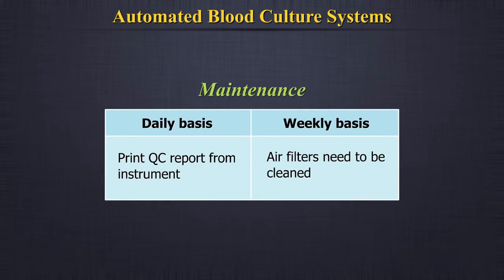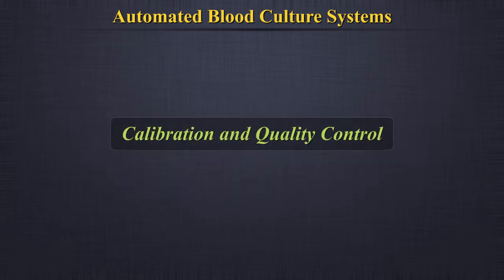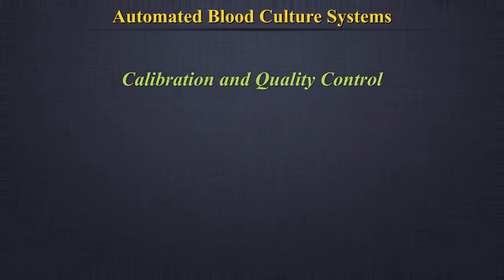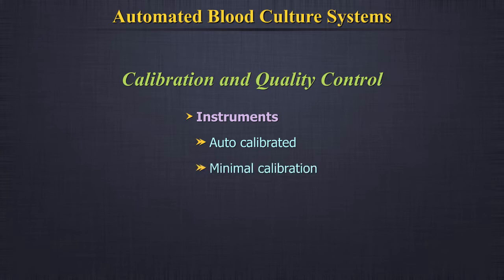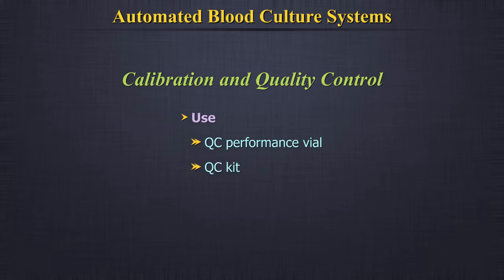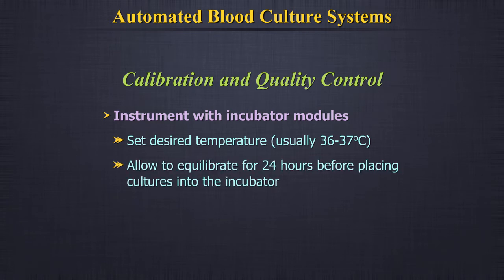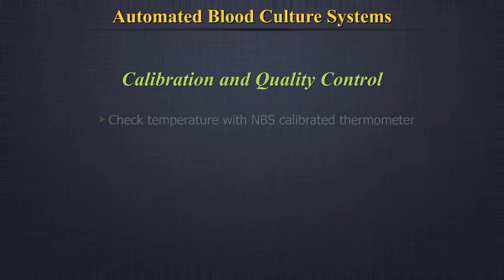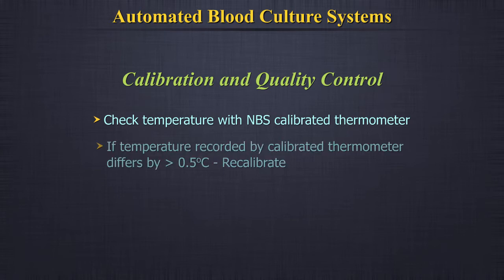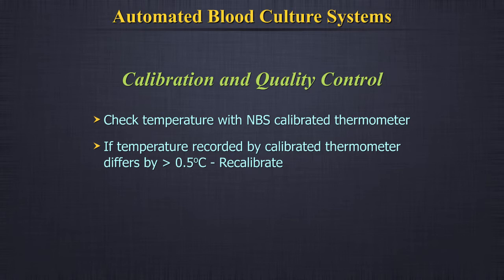Daily or weekly maintenance: on a daily basis, it is required to print the quality control report from the instrument, and on a weekly basis, air filters need to be cleaned. Calibration and quality control: the manufacturer will provide a service representative to perform initial installation and calibration of the instrument. Instruments are either auto-calibrated or require minimal calibration by the user. Use quality control performance vials or quality control kits to calibrate instrument detection systems as recommended by the manufacturer. For instruments with incubator modules, set the desired temperature and allow it to equilibrate for 24 hours before placing cultures into the incubator. Check temperature with an NBS-calibrated thermometer; if the temperature recorded differs by more than 0.5 degrees centigrade, recalibrate by following instructions in the operator manual.